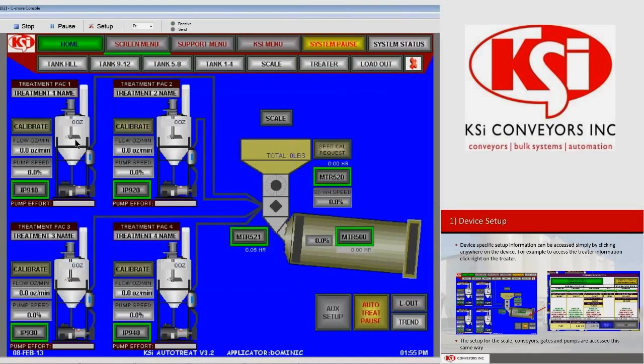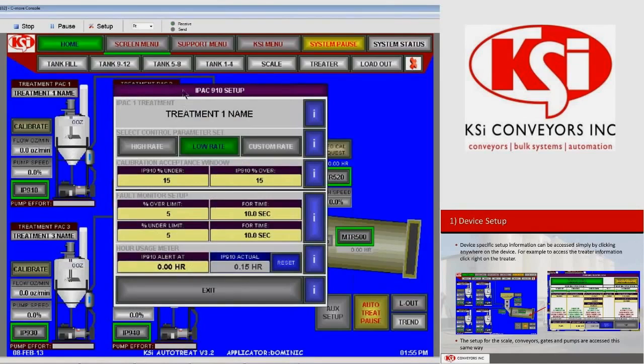Each treatment pack, as we call it, also has some settings for it, and these are accessed just by clicking right on the tank. So if we click on this tank, it opens up an IPAC 910 setup. That's the one we clicked on, and we have some settings here that are specific to each mixed tank or treatment tank. First of all, we can set which pump we have. If it's a high rate or a low rate pump, we just toggle back and forth between these 2 buttons.